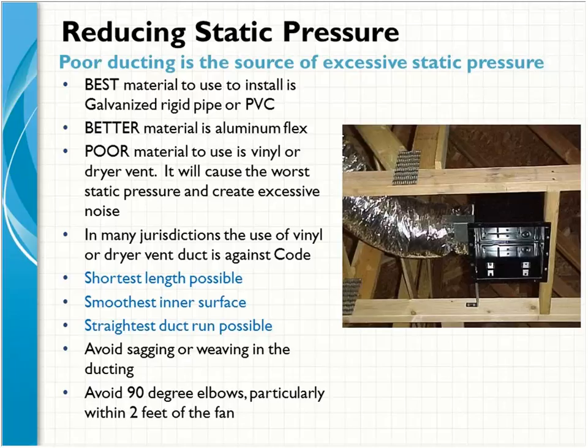Years ago, people would use those silver vents that were in the soffits as a termination, and those things have a real tight screen on them and would plug up real fast. So not only do we need to keep our ductwork short and keep it straight by reducing the number of elbows, and preferably if we can use a smooth ductwork like a galvanized pipe or PVC, but we also want to make sure that the termination that we're connecting to the end of the ductwork doesn't offer a lot of resistance.